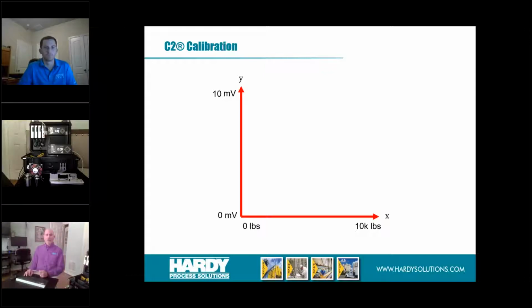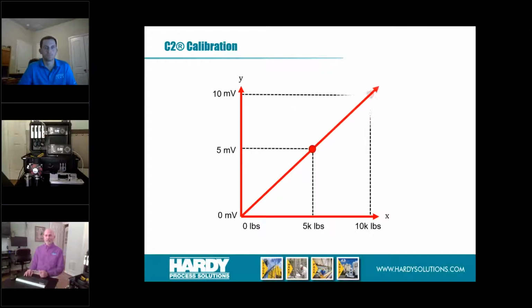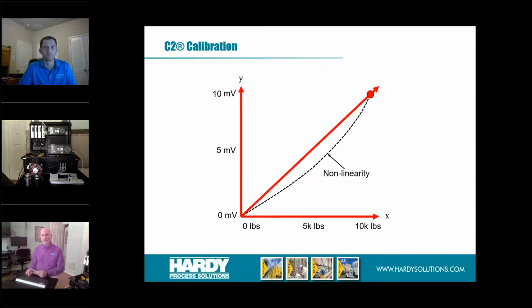So in a perfect world, a perfect scale would have a straight line slope, which would go straight through 5,000 pounds at 5 millivolts, 10,000 pounds at 10 millivolts. But in the real world, you're not that linear. You're going to have some error in that scale. And so this is where, when we do a traditional calibration, the technician is trying to capture this non-linearity that we have.